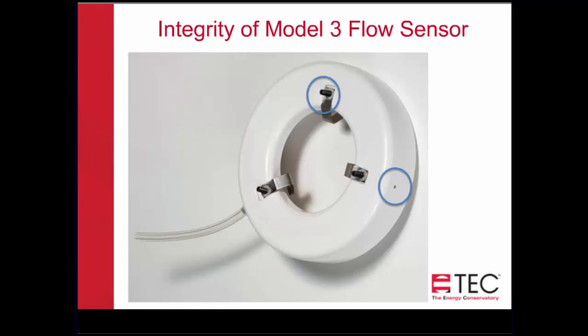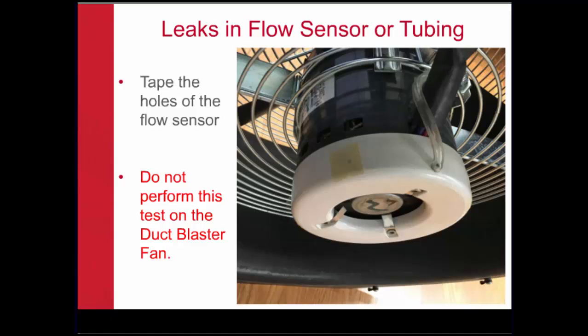So one of the things we want to do is test the integrity of that Model 3 flow sensor. The process is where you want to tape over the holes of the pressure sensor. Hopefully you can see that there's a small piece of masking tape over one of the holes, and there are 4 holes around the flow sensor. Now, one of the things we do not recommend is doing this test with a duct blaster fan. The duct blaster fan has a very different pressure sensor. It's a stainless steel tube, and it is extremely difficult to accurately put tape over those holes, and much less get that tape back off again. So we do not recommend doing this test with the duct blaster. This is only for the blower door.